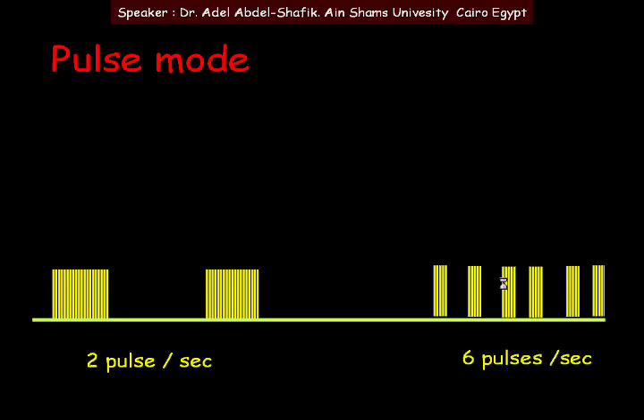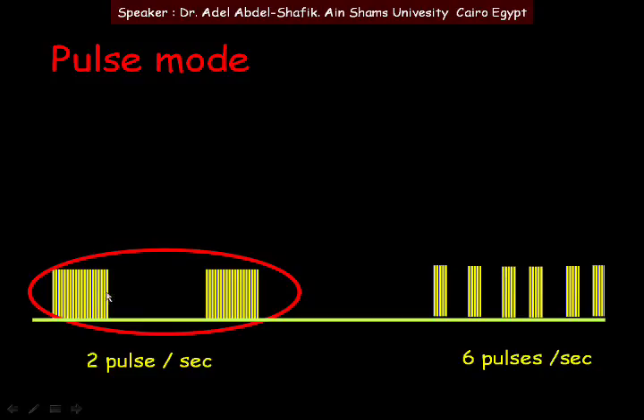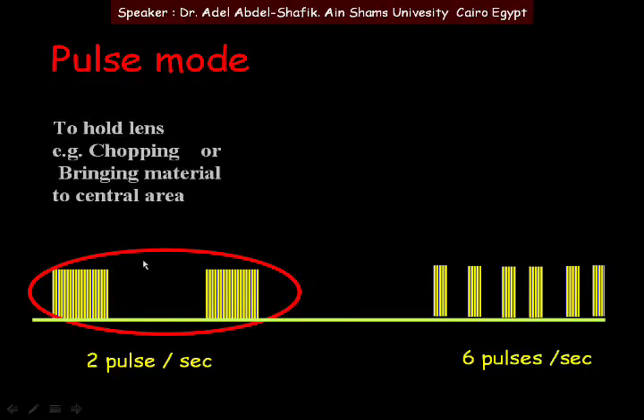Pulse mode can be set to two pulses per second or six pulses per second. At two pulses per second, we have long on and long off periods. The long off period is useful for holding lens material — important for chopping or bringing material to the central pupil area before removal.